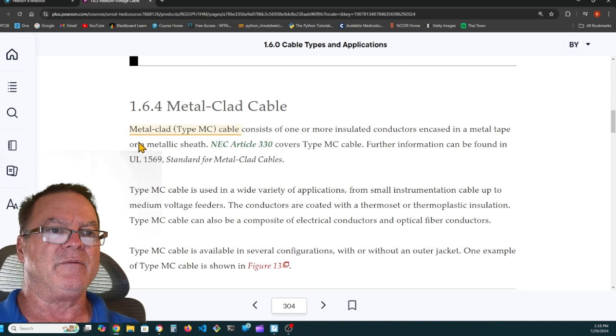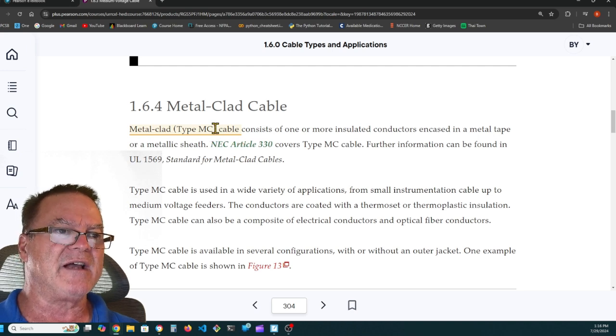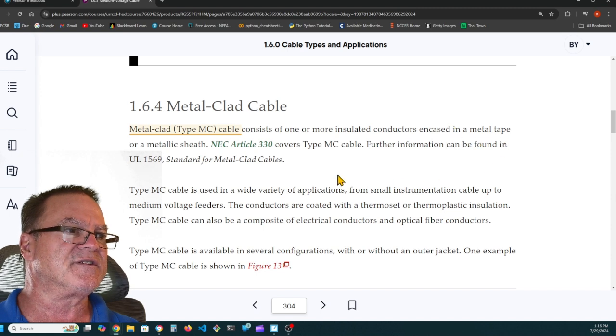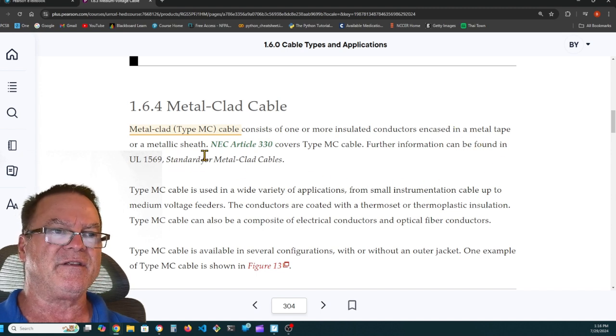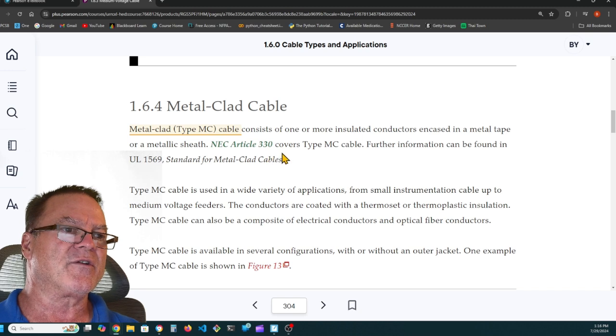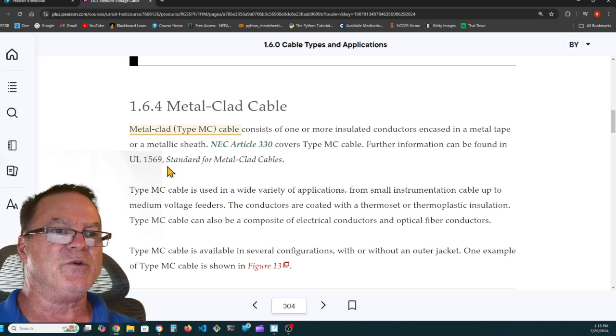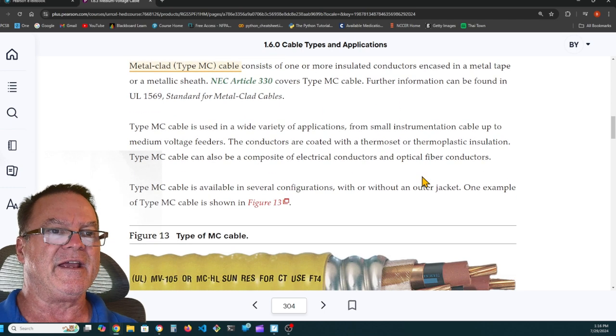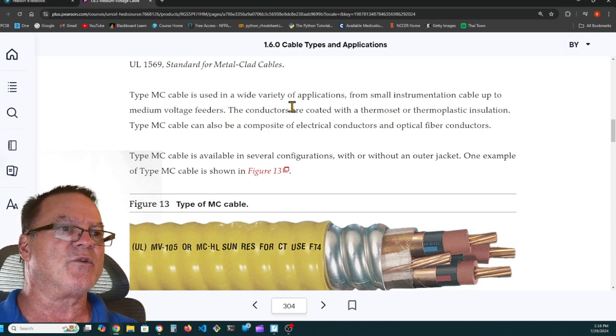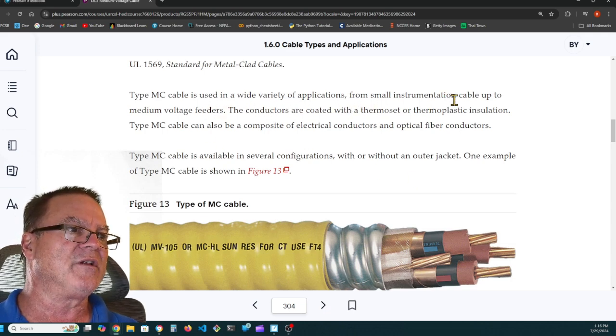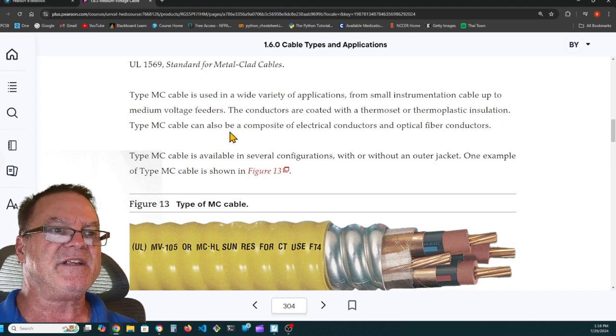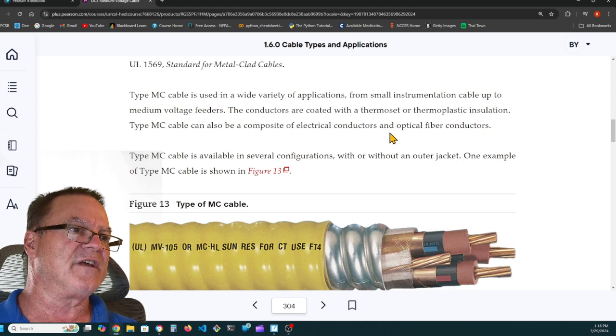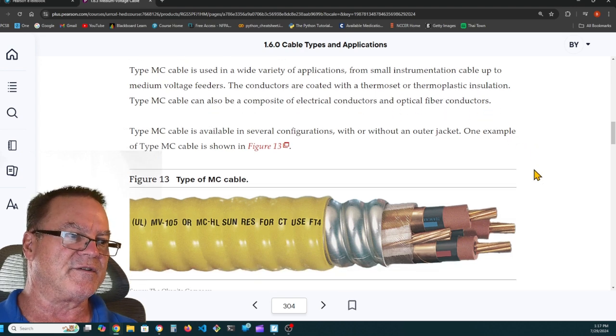1.6.4 Metal-Clad Cable. Metal-Clad type MC cable, that's highlighted, consists of one or more insulated conductors encased in a metal tape or a metallic sheath. NEC Article 330 covers type MC cable. Further information can be found in UL 1569, the standard for metal-clad cables. Type MC cable is used in a wide variety of applications, from small instrumentation cable up to medium voltage feeders. The conductors are coated with a thermoset or thermoplastic insulation. Type MC cable can also be a composite of electrical conductors and optical fiber conductors.